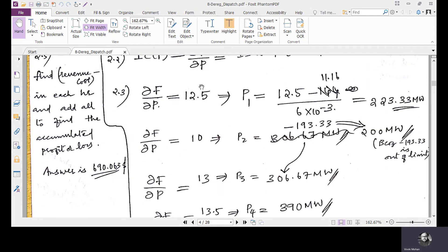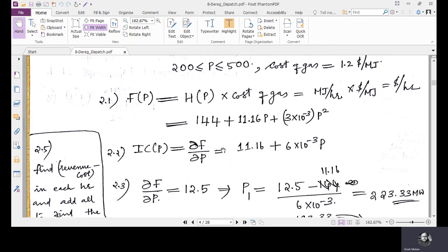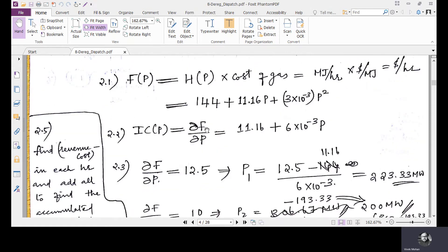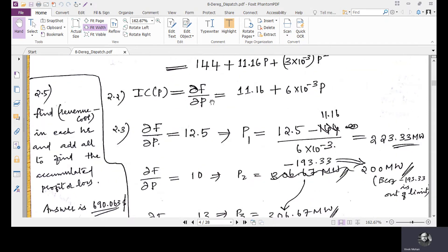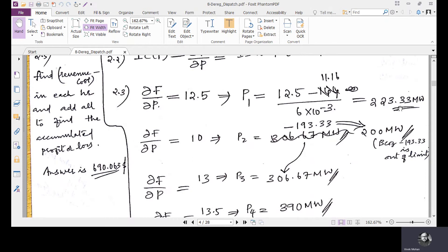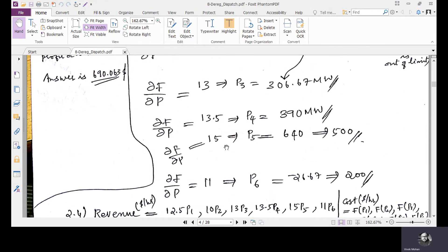Setting dF/dp equal to the system marginal price for each hour: for hour one, 12.5 = 11.16 + 6×10⁻³ × p1, so p1 = (12.5 − 11.16) / (6×10⁻³) = 223.33 MW. For hour two, dF/dp = 10, giving p2 similarly. This process is repeated for all six hours to find the corresponding megawatt output each hour.